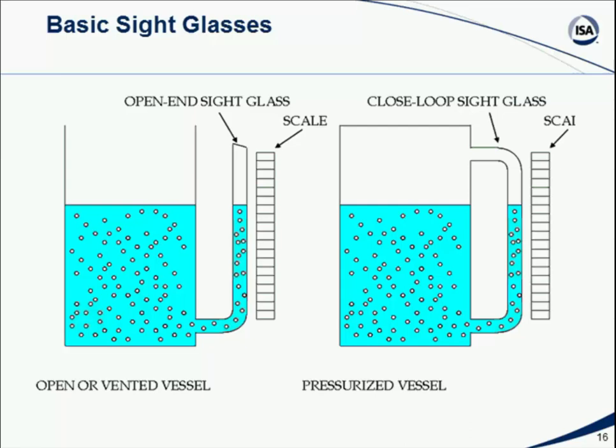Now, the same kind of technology can be used if you have a closed pressurized vessel. The only difference in that case, and we see this in the diagram here on the right, is that we have the tank fully sealed, and the sight glass itself continues up and then enters the top part of the tank above the fluid. Now, if we presume that this is a pressurized vessel because above the liquid we've got some kind of vapor, and that vapor based on temperature is exerting a downward pressure, well, that downward pressure is pushing down on the liquid in the vessel and equally downwards on the fluid in the column in the sight glass. So again, just as if the whole thing was vented to the atmosphere, the level in the sight glass will be the same level as the fluid in the tank.